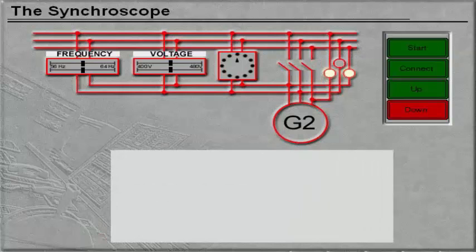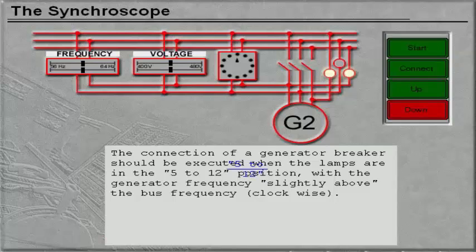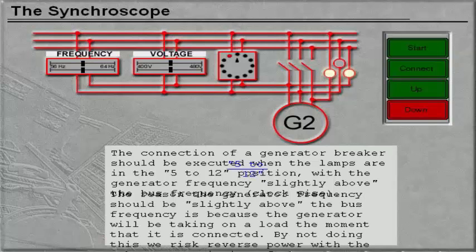The connection of a generator breaker should be executed when the lamps are in the 5-12 position, with the generator frequency slightly above the bus frequency, clockwise. The reason the generator frequency should be slightly above the bus frequency is because the generator will be taking on a load the moment that it is connected. By not doing this, we risk reverse power with the subsequent tripping of the generator breaker.